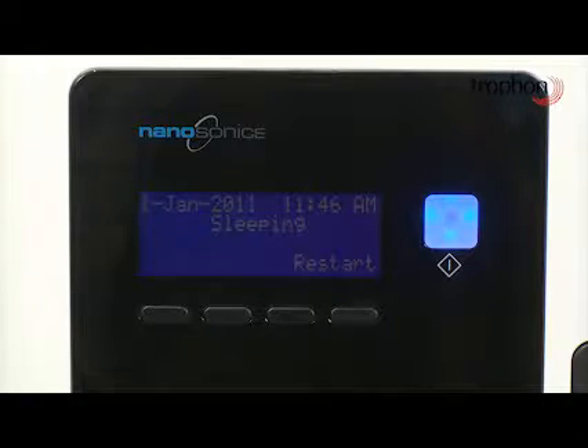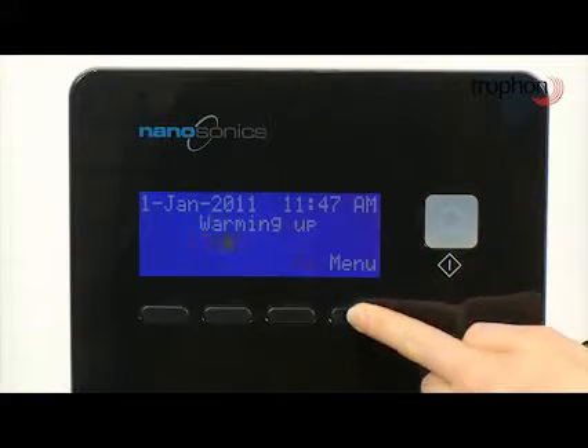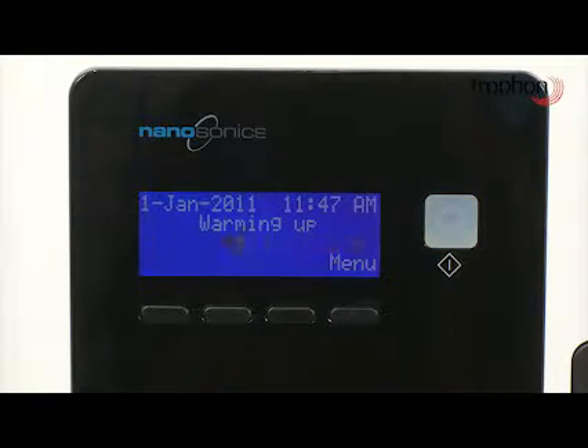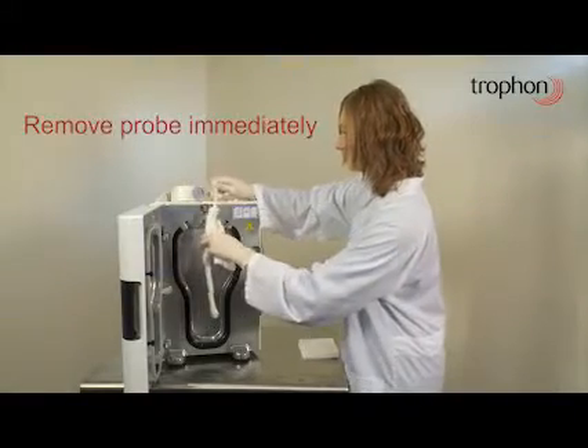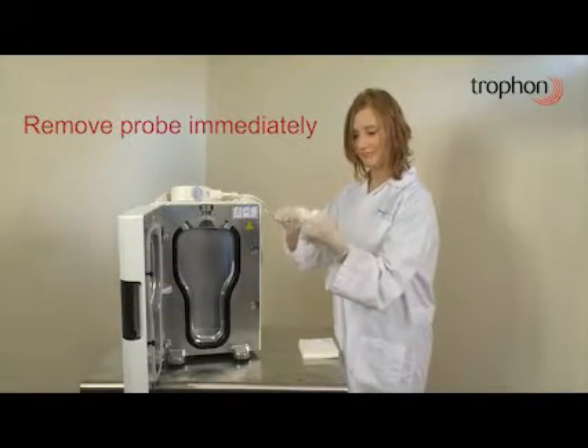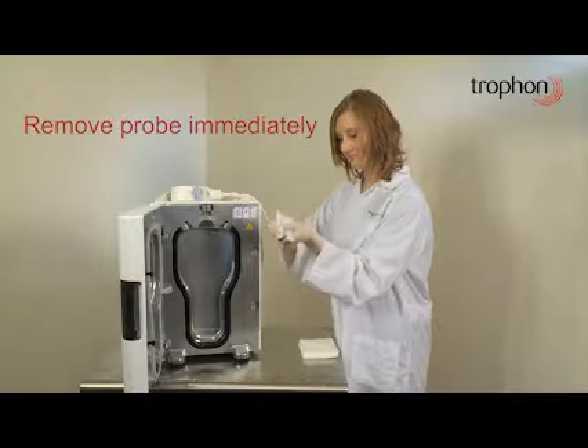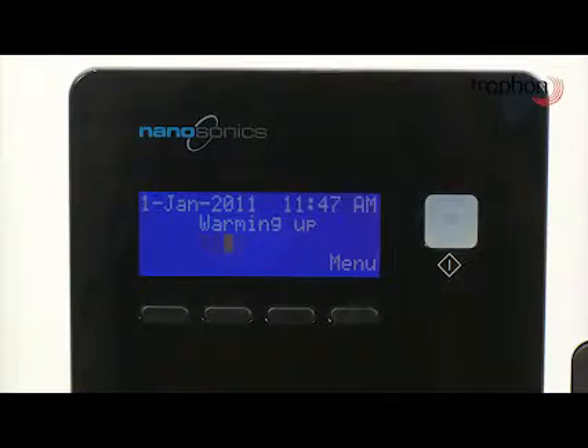After 2 hours of inactivity, or if the probe is not removed immediately after a disinfection cycle, the device will enter sleep mode. To exit sleep mode, press Restart on the LCD screen. The warm-up time from sleep mode is approximately 10 minutes. To prevent the device entering sleep mode, always remove the probe immediately after a disinfection cycle. If the device has been powered off, warm-up time will be extended.